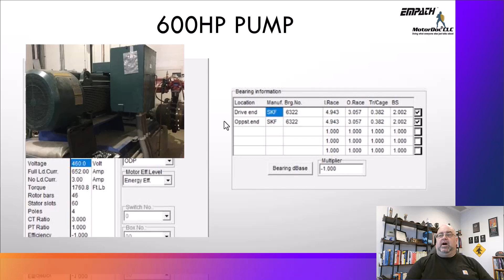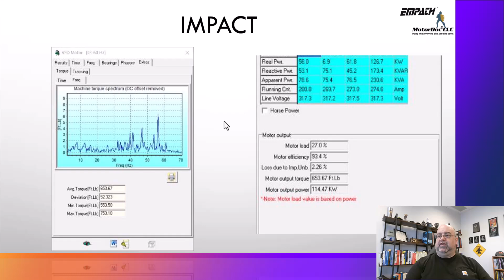So let's take a look at a 600 horsepower pump motor on an inverter. I've used this example a few times, so you might have seen it before. It had a couple of problems - a bearing issue, soft foot, which we'll take a look at, and an impeller issue as well. So we noted those, and here they are.